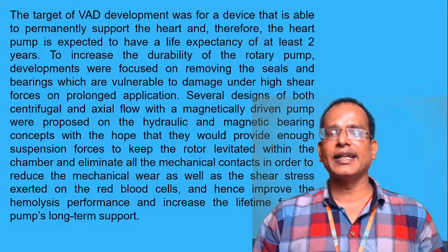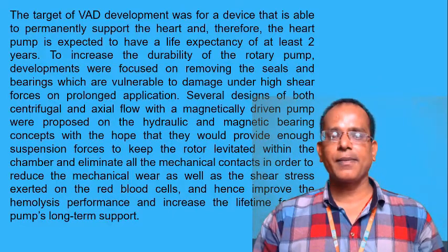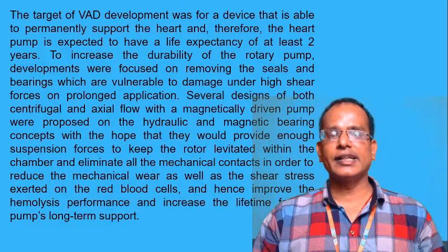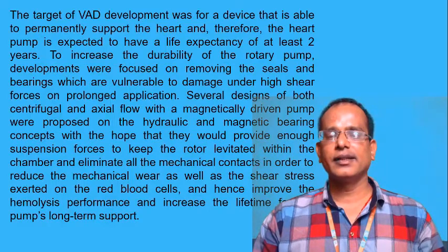Several designs of both centrifugal and axial flow pumps with magnetically driven rotors were proposed on the hydraulic and magnetic bearing concept, in the hope that they would provide enough suspension force to keep the rotor elevated within the chamber and eliminate all mechanical contact, in order to reduce mechanical wear as well as shear stress. It is also gentler on the red blood cells, and hence it improves hemolysis performance and increases the lifetime of the pump for long-term support.